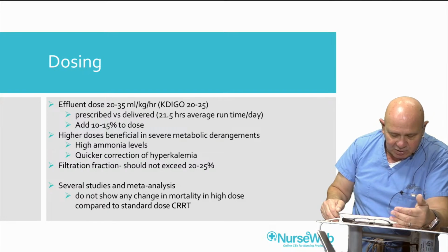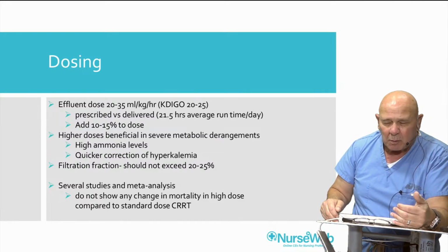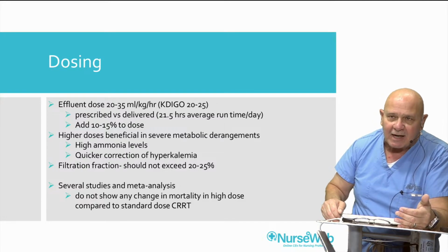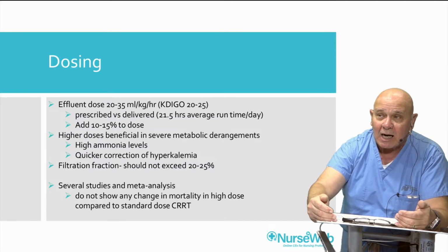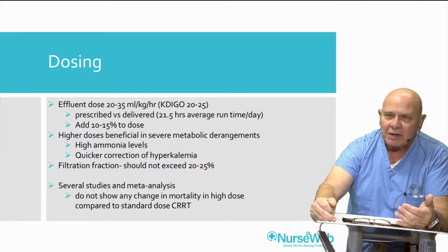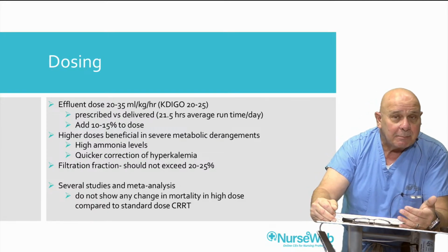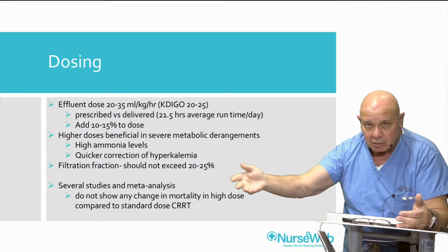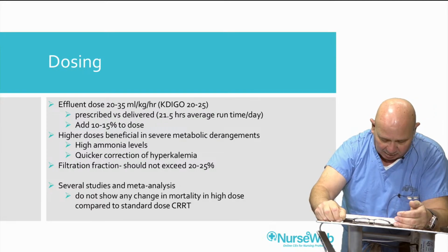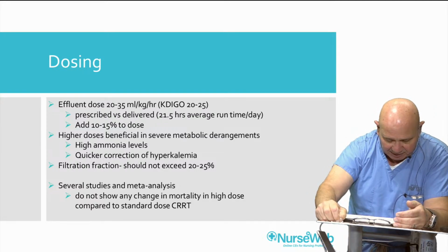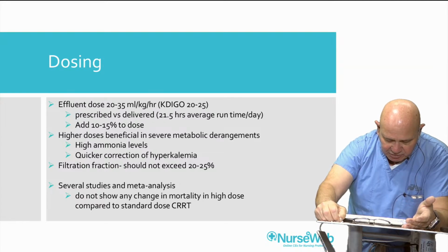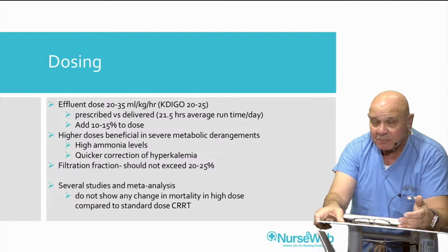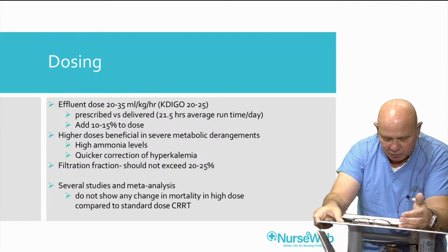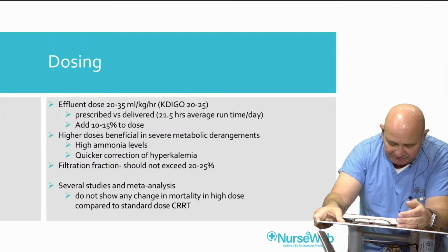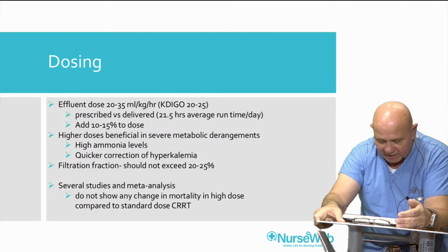So they recommend going up 10 to 15% of your prescribed dose to accommodate the fact that you're going to have interruptions. It's a 24-hour-a-day therapy, but you're only going to have 21.5 hours in the best of circumstances because of just naturally having to stop the therapy during the course of the treatment. Higher doses are beneficial in severe metabolic derangements if you have very high ammonia levels, quicker correction of hyperkalemia. But it's very important: the filtration fraction should not exceed 20 to 25%.